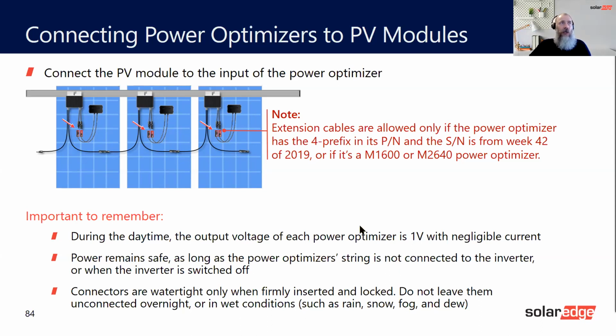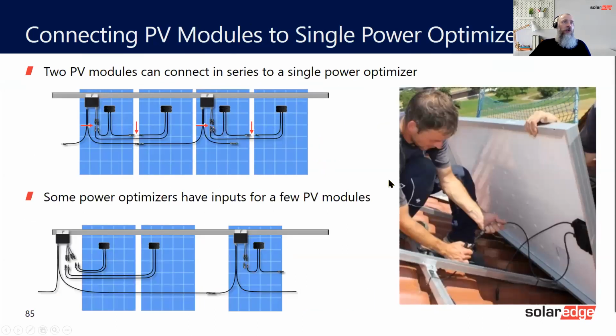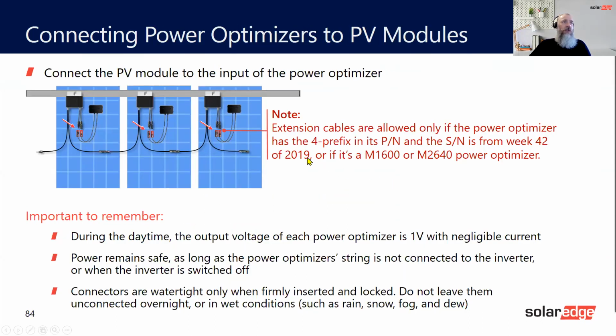That's perfectly allowed. One of the other things that have changed is that if you have an optimizer that has 4 in the prefix of the part number, or is from 4219, you're allowed to extend that up to 8 meters on the plus and 8 meters on the minus. The compact ones, if you're familiar with those, you can extend those up to 10 meters. Okay. Not on the M1600 though.